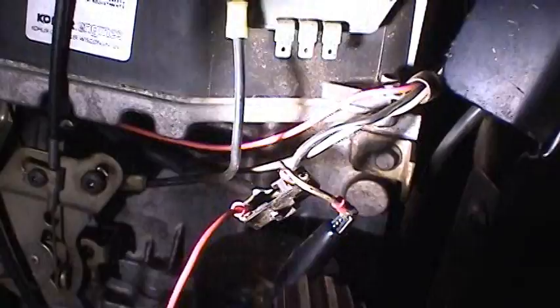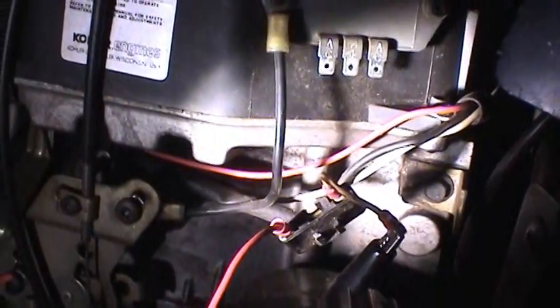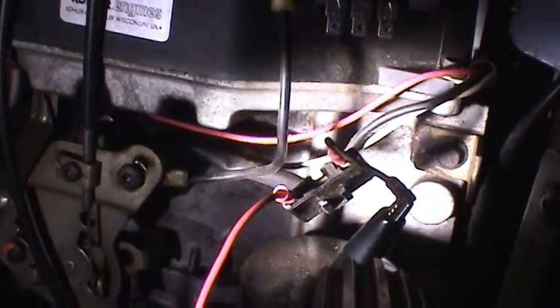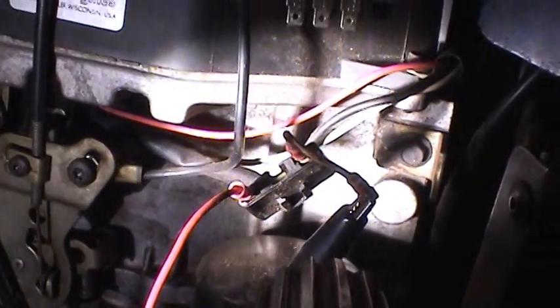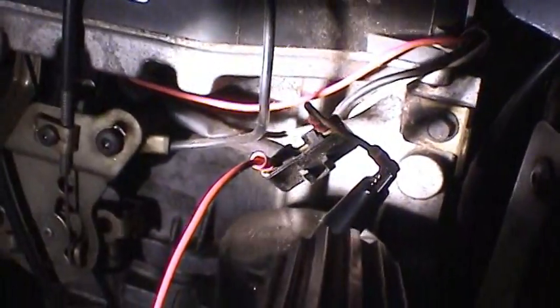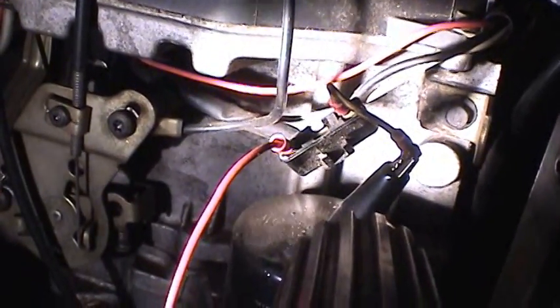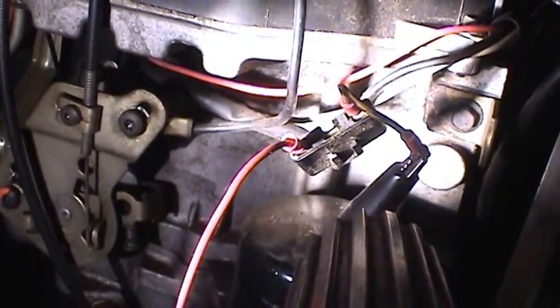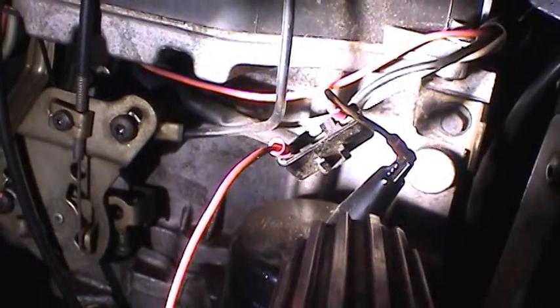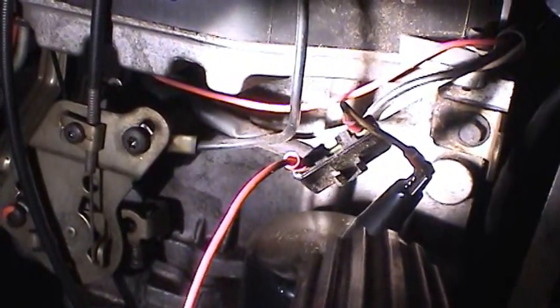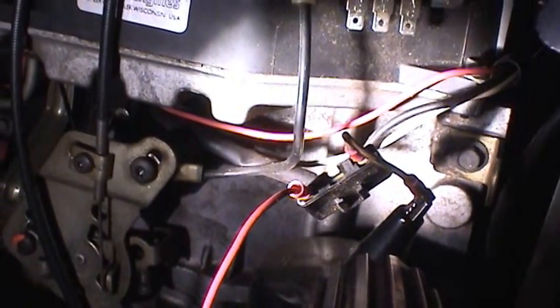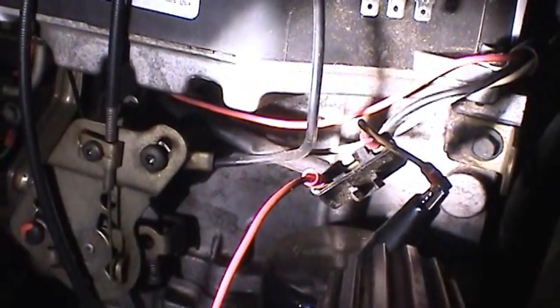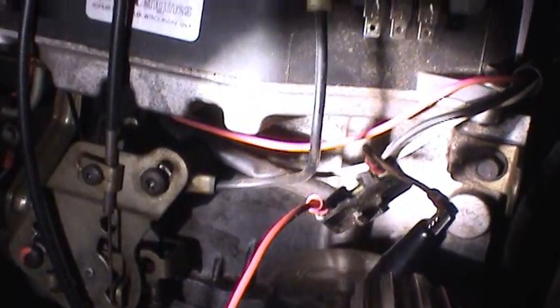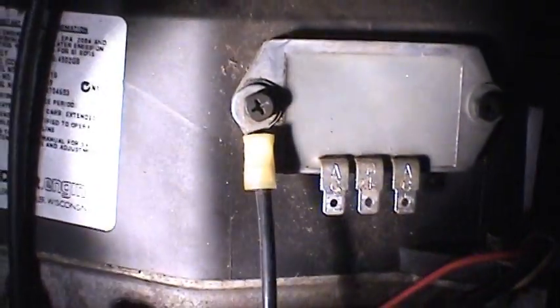While I'm back, still troubleshooting this, I had one more idea: to see if I have enough current coming off the stator and that alternator to drive a load. Even though I had about 24 to 35 volts, depending on engine speed, coming off that stator, that doesn't necessarily mean it's got enough current carrying ability to do any good. It could be burned up wiring or high resistance in the wiring. So before I waste money on a new voltage regulator module, I've got a 24 volt lamp to test it with.